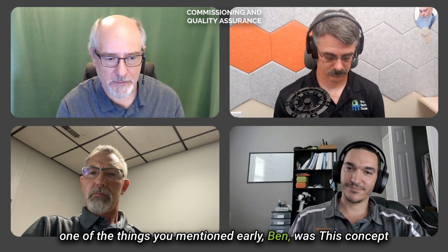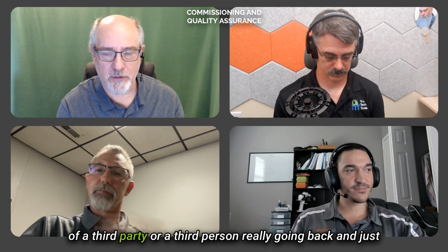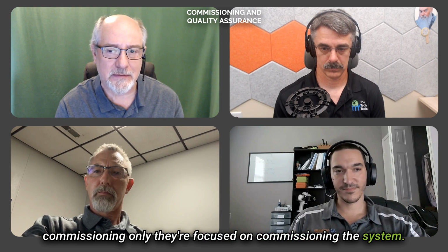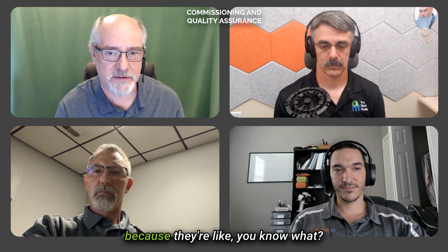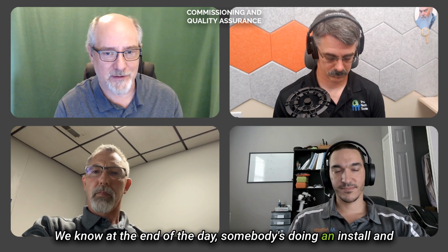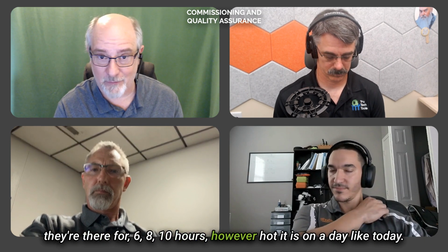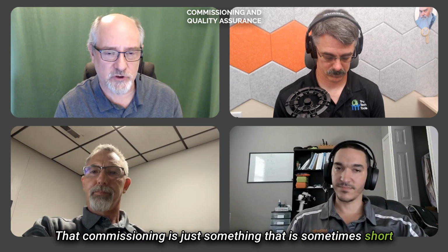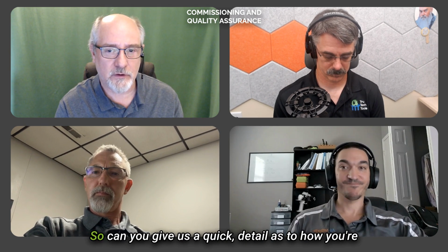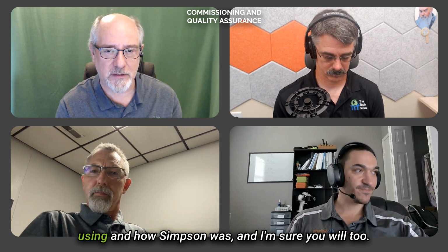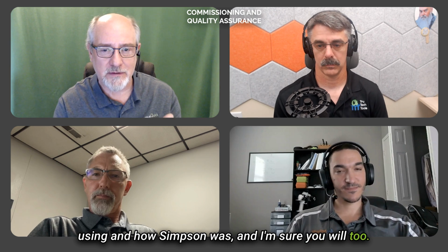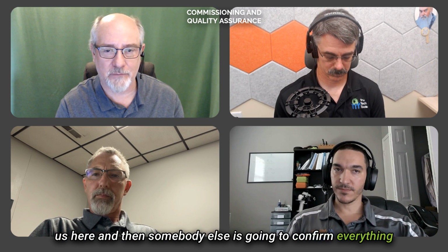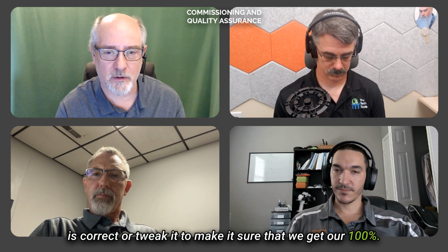One of the things you mentioned early, Ben, was this concept of a third party, a third person coming back and commissioning only. They're focused on commissioning the system. That's a new concept for many companies, because at the end of the day, somebody's doing an install and they're there for 6, 8, 10 hours, however hot it is on a day like today. That commissioning is sometimes shortchanged because they just want to get the heck out of there. So can you give us a quick detail as to how you're using it, and how Simpson was, and I'm sure you will too: this commissioning concept is get us here and then somebody else is going to confirm everything is correct or tweak it to make sure that we get our 100%.